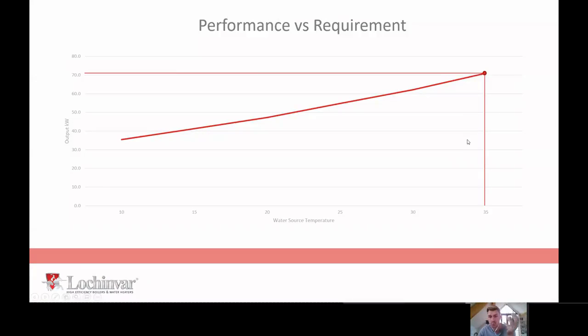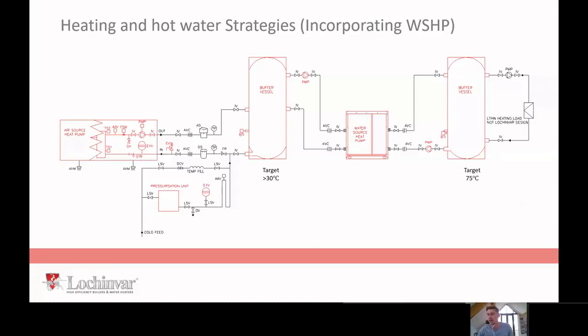So what we do quite frequently on existing buildings where we don't want to mess about too much with the existing emitters, we have an air source heat pump serve a thermal storage vessel, and we take that thermal storage vessel up to 30 or 35 degrees. The water source heat pump will then take that 35 degrees from the thermal store. It doesn't care, it thinks it's a lake. It's not, it's a thermal store. It takes that 35 degrees and takes it up to any temperature you want, up to 80 degrees centigrade.